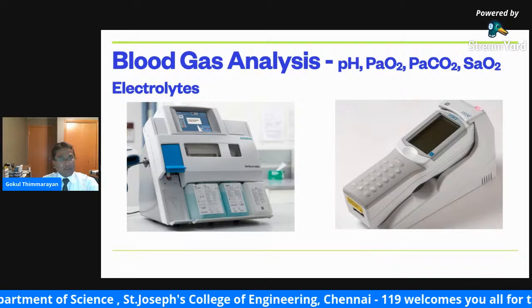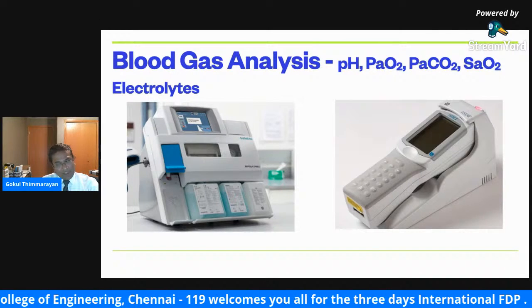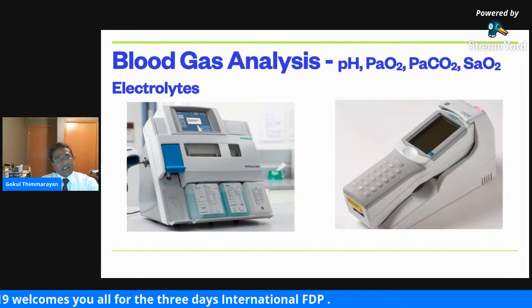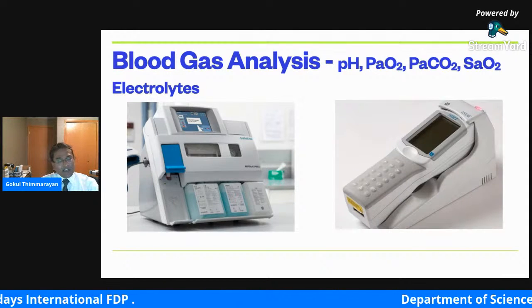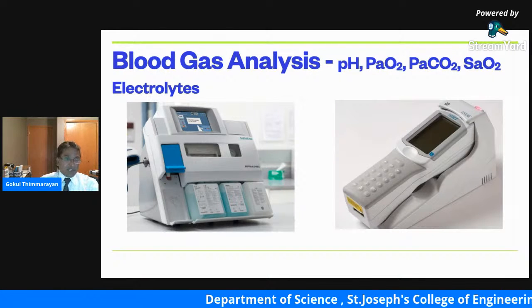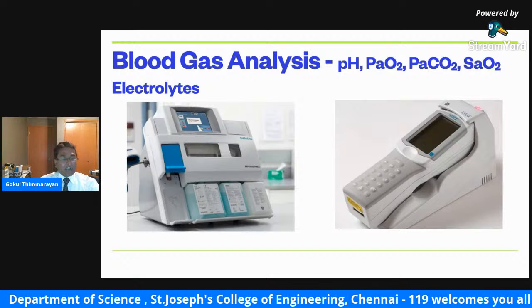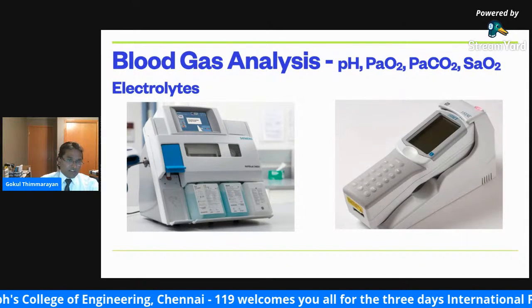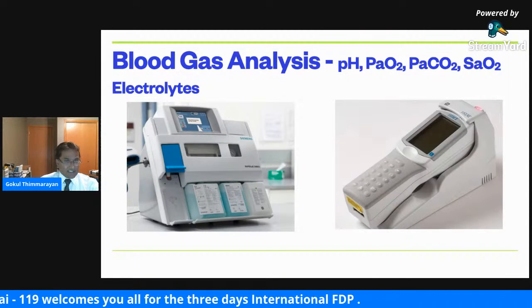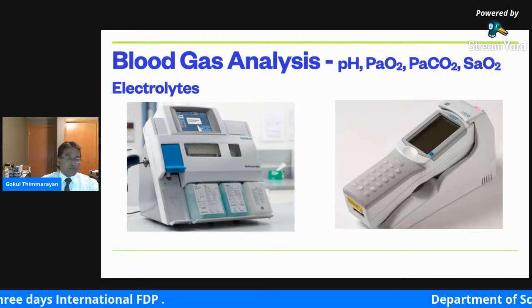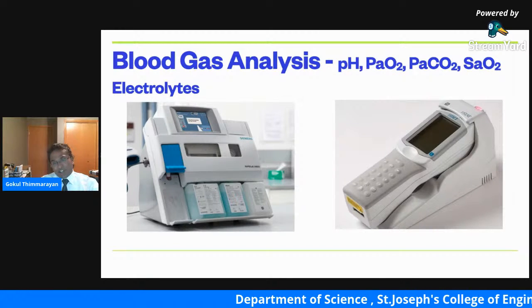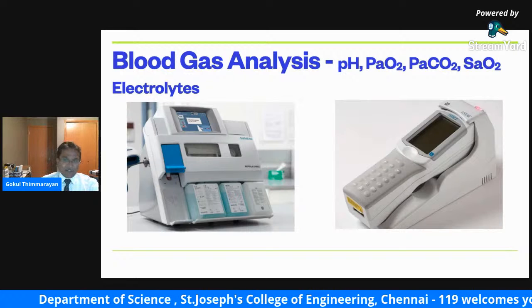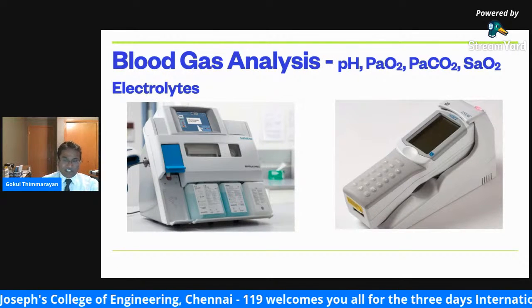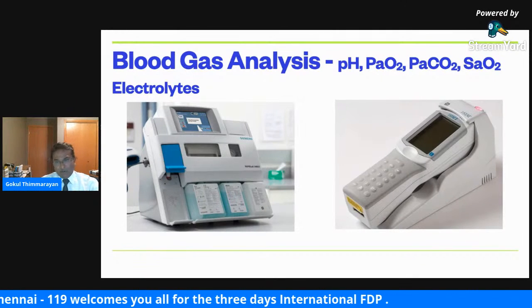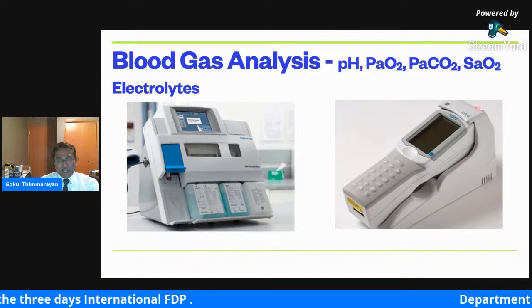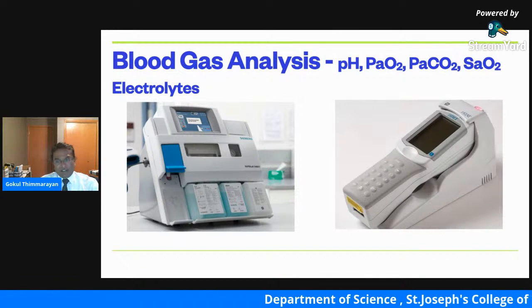And next comes the blood gas analysis. So after the therapy, apart from the pulse oximeter, we analyze directly from the blood the partial pressure of oxygen, carbon dioxide, and various other parameters. Literally, this blood gas analyzer machine gives hundreds of parameters. It gives almost everything. The device on the left side of the screen is the standard blood gas analyzer machine, which is used in laboratories to do analysis and give the report. And the one that's the iStat machine from Abbott Industries is a handheld device. It's put on its charger, but when we lift it, it's almost like a cordless phone, or a little bit bigger than that. This device gives the same hundred-odd parameters when we have to analyze.